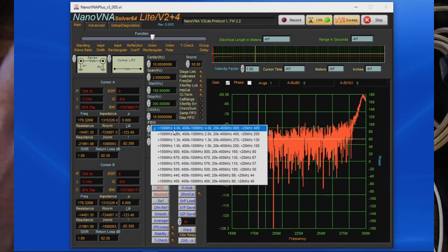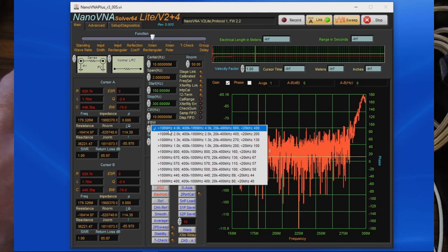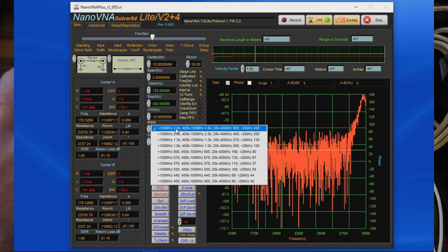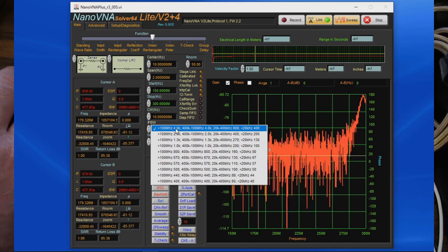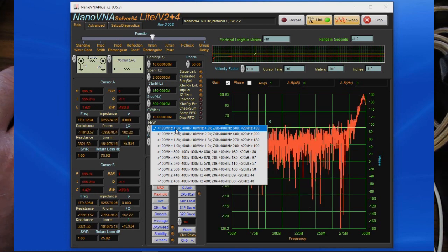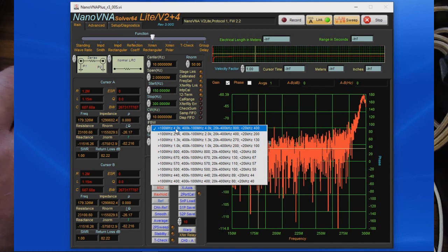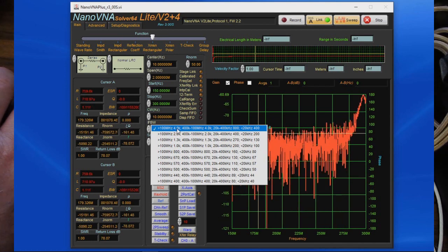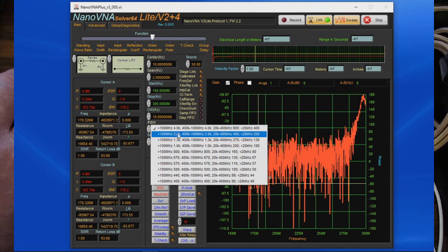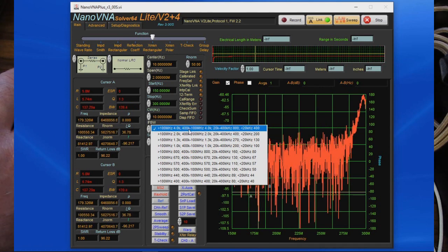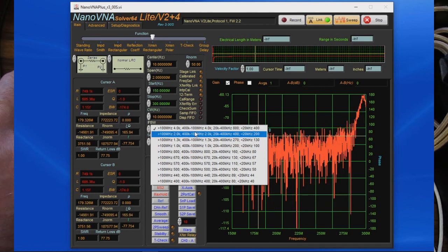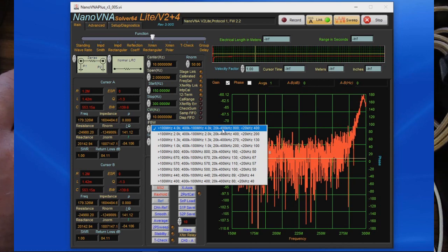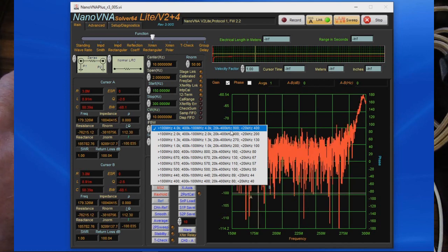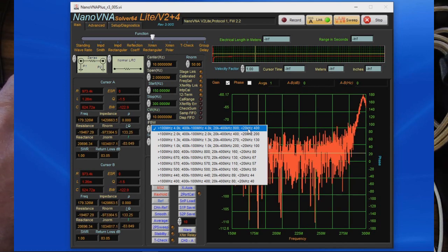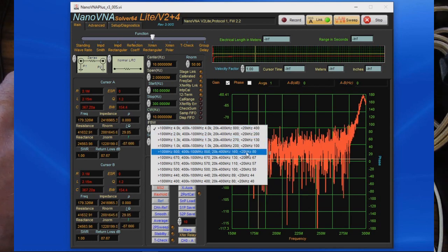The way the firmware works is he has 4 different bands assigned. Each band has its own unique IF filter. So for example, the very first selection, or an average of 1, gives you an IF bandwidth of 4 kilohertz for anything greater than 100 megahertz. For 400 kilohertz to 100 megahertz, it's 4 kilohertz. 20 kilohertz to 400 kilohertz, it's 800 hertz. And less than 20 kilohertz, it's 400 hertz.